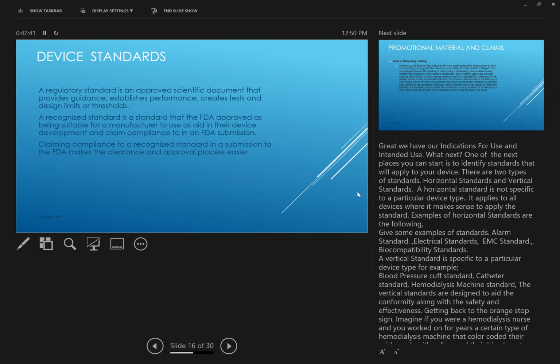Yeah, so it's my point. A lot of these startup companies don't realize there are third-party test sites, like TUV. You'll see Intertek mentioned, and UL. You'll see the UL standard for electrical equipment. All these different labs are out there as third-party test sites or test houses. So one thing you want to establish when you're developing a device, once you get it to a certain point, maybe during feasibility, is to work with the test house you're going to use, so they can see the device too. They can test it, and they may give you some advice on how to make it better.